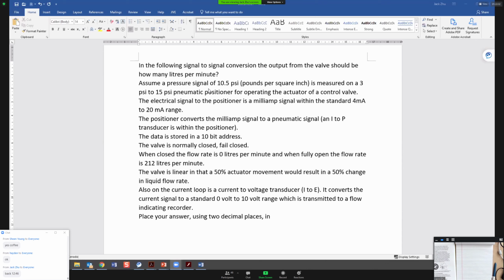So the words are really long. Following signal-to-signal conversion, the output from the valve should be how many liters per minute. So that's what we want to find, the liters per minute, right? He said a pressure signal is 10.5 psi, measured on a 3 to 15 psi positioner for the operator actuator of a control valve. The electrical signal to the positioner is a milliamp signal, standard 4 to 20 milliamp. The positioner converts the milliamp signal to a pneumatic signal. The data is stored in a 10-bit address. The valve is normally closed. Fail to close.